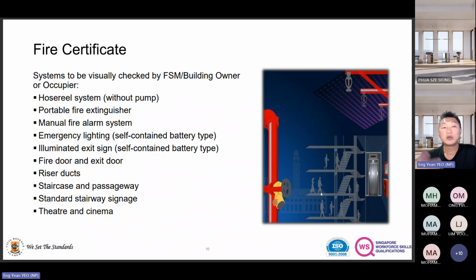Usually during inspection, if there's a riser door, please try to open it up and take a look whether anyone stored any other stuff inside, especially paint - people want to put it there so it's not unsightly, but they forget it's actually flammable material. As the FSM, when we walk around the building, riser doors are one of the things we need to open and check, as much as possible.